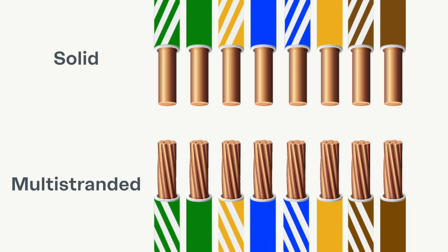First of all, let's talk a little bit about the different cable types that are out there. As you may know, for the Cat cables, there are solid strand cables, also called installation cables, or there are also multi-strand cables, which are often called patch cables. However, for our installation, we always recommend you to use solid strand cables. These installation cables have two big advantages. First of all, they are mechanically safe, so especially when you draw the line through a cable lug, for example, or through a wall, there is a lesser opportunity that these cables will break and you lose data communication.